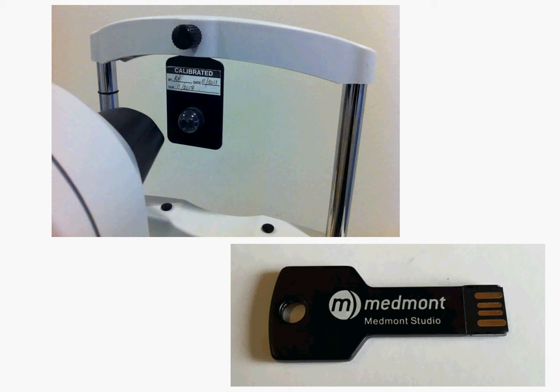Start by affixing the calibration device to your Medmont instrument. Take the flat metal plate and insert it up and into the forehead rest with the ball facing the instrument. Then with the small black screw, insert it through the hole and into the metal plate, securing it tightly.